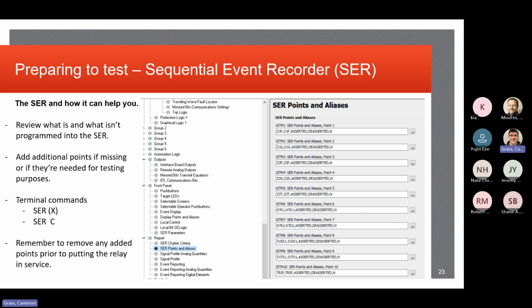We also utilize the SER command specifically in the situation where we provide data during testing so that we see specific elements pick up, time-stamped events taking place during our actual testing. And we usually save those and provide those with our test set results after our relay testing is complete.